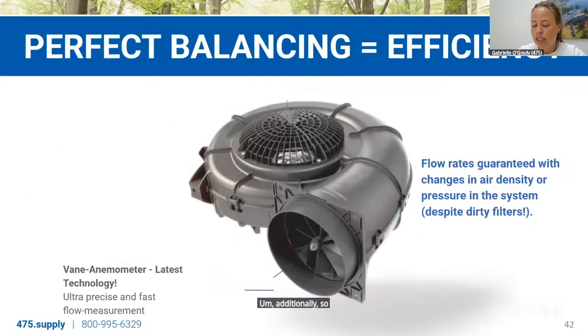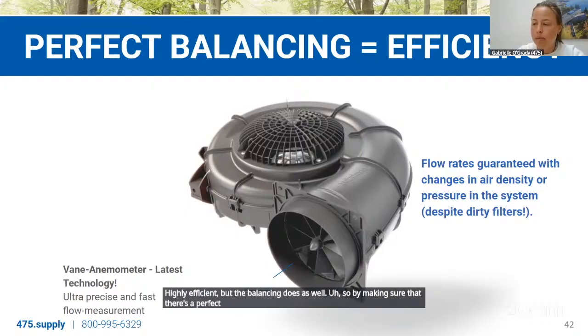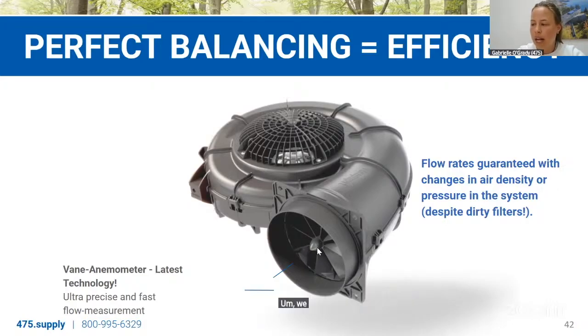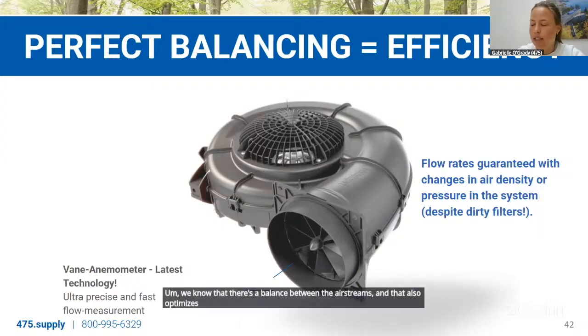Additionally, not only does the core help make the system highly efficient, but the balancing does as well. By making sure that there's a perfect mass balance between the supply and exhaust air, using this vane anemometer, which is right at the end of the fan on both fans, we know that there's a balance between the air streams, and that also optimizes the heat recovery.